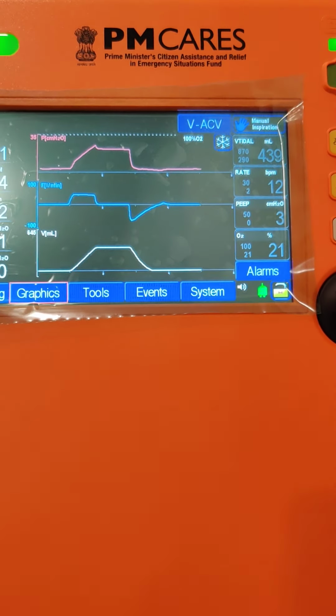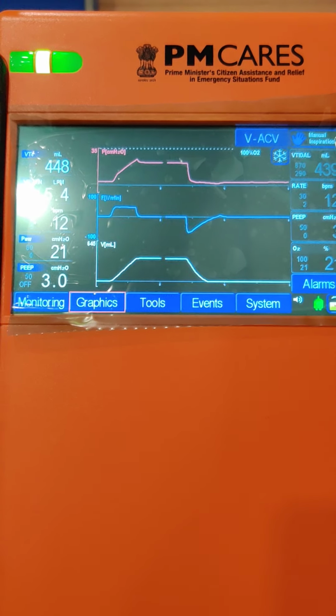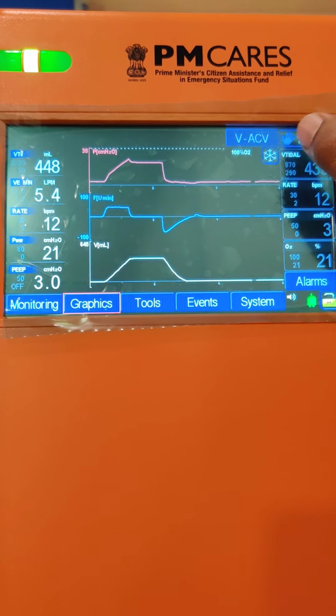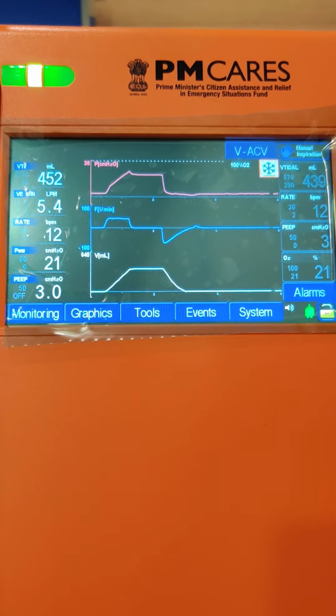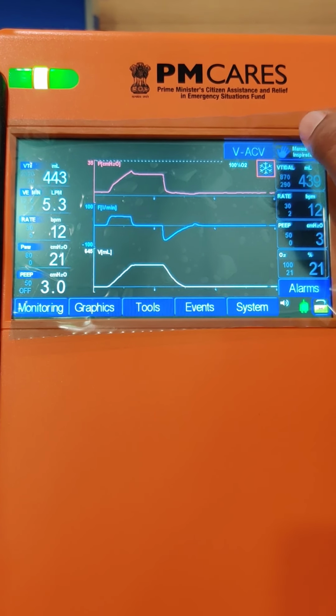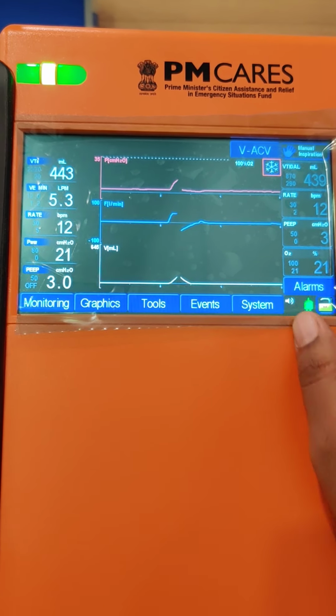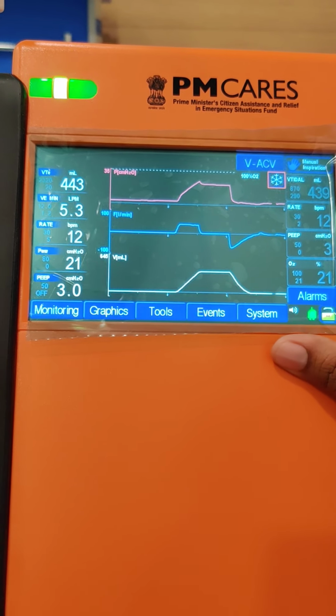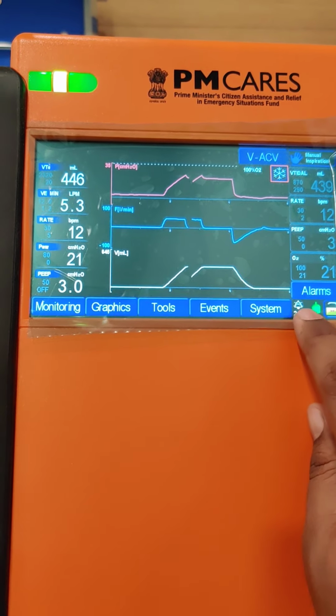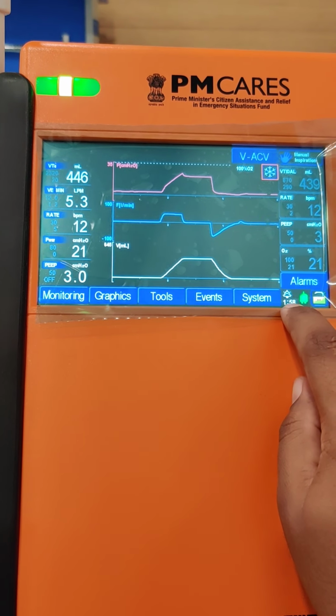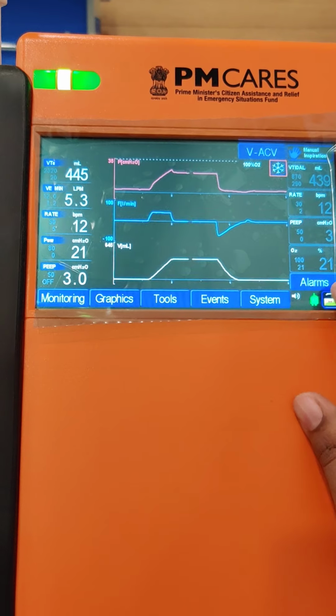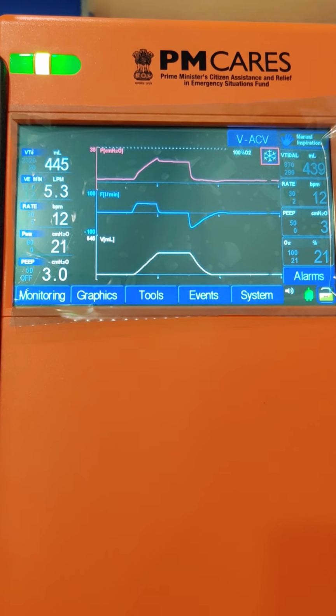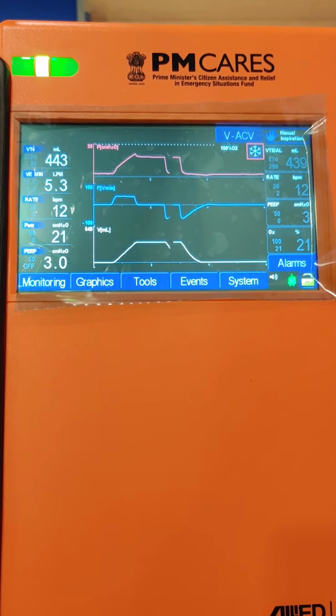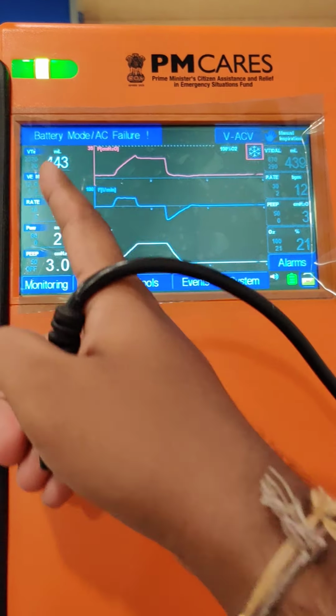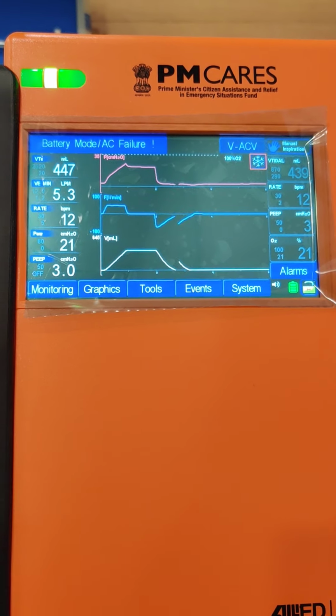Now I am showing you the different symbols, the indications which come on the ventilator. This I have already discussed. This is for freezing the waveforms. If you want to analyze the waveform, you can freeze it with the help of this button. Then this is for alarm silence and alarm reset. If you silence the alarm for 2 minutes, this symbol will come over here with a countdown timer. And this shows the mains supply is connected. If I remove the mains from here, it will show the battery like this, and the notification will come on the top also that battery mode has been activated.